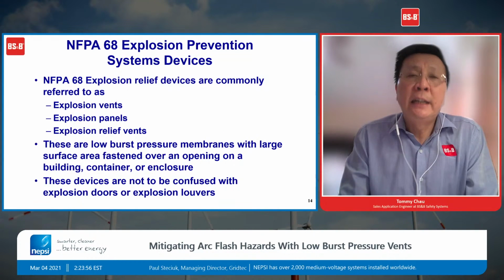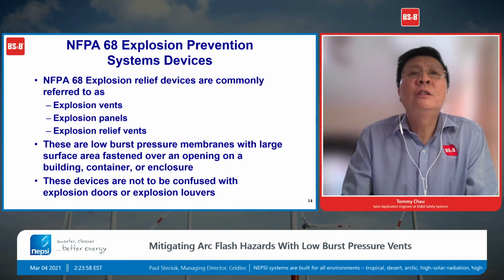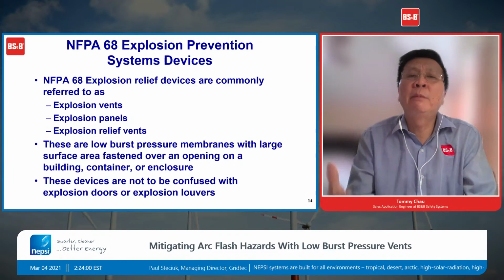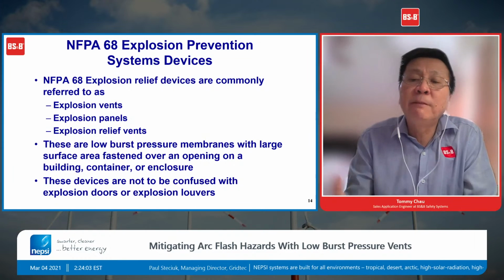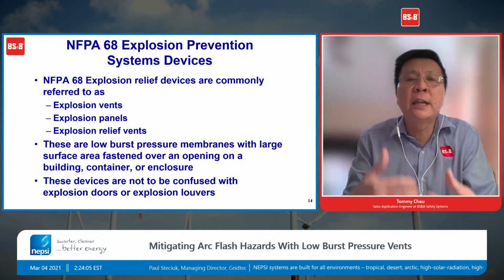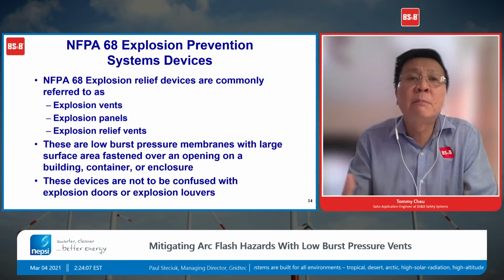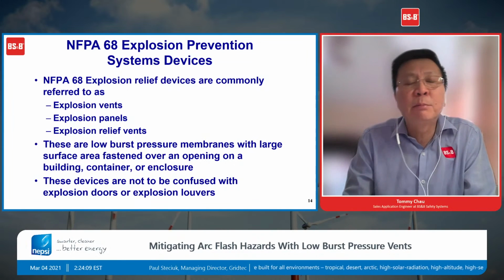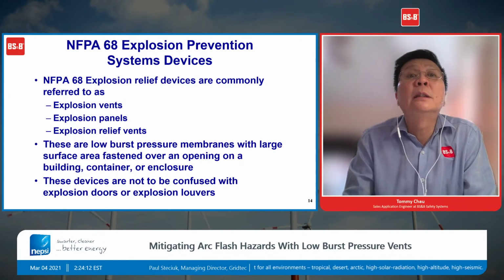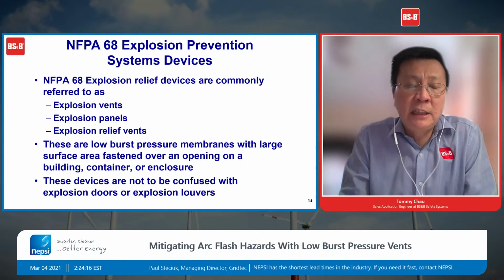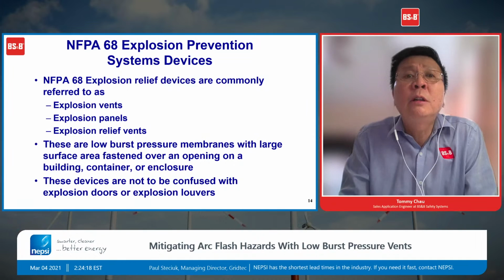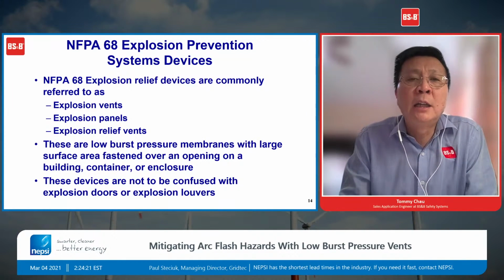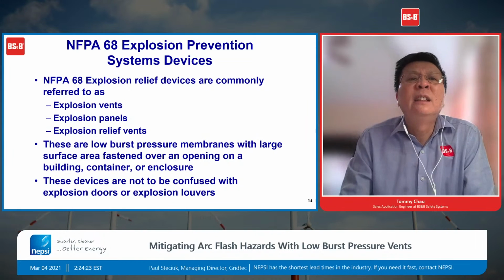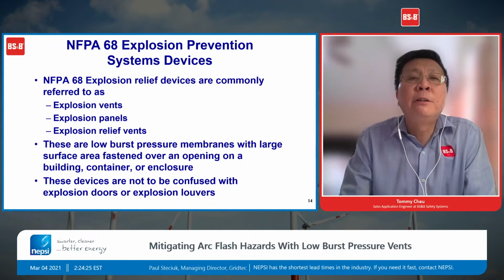Okay, NFPA 68, again, covers explosion vent and prevention system devices. So we have explosion vent, explosion panel, explosion relief vent. These are all the same product. It's just that some people refer to them as panel, some people refer to them as relief vent, but they are not the same as the explosion door or explosion louver. Explosion vent and explosion panel are non-reclosing devices. So not to be confused with the explosion door.